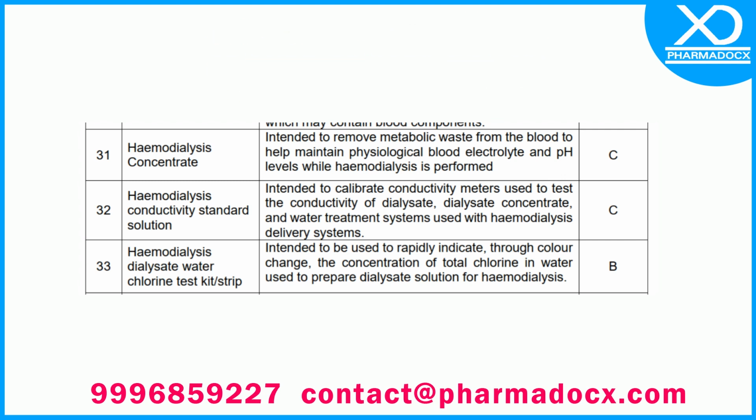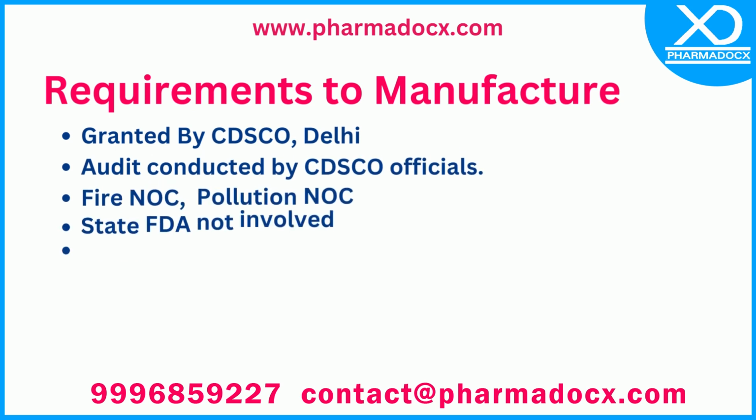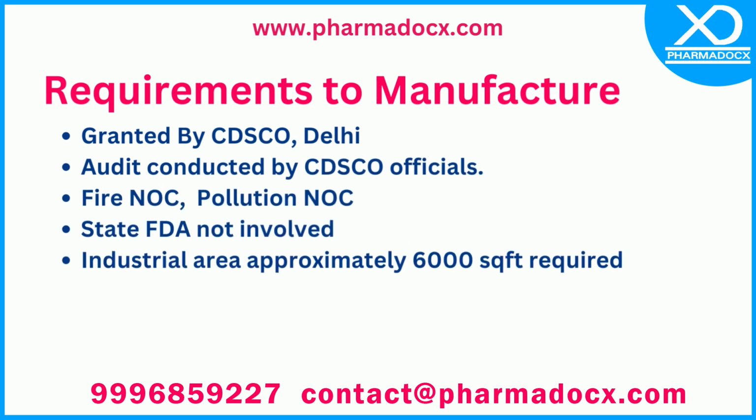Now let's discuss about requirements for manufacture of class C medical devices. The license to manufacture is granted by CDSCO headquarters in Delhi. The license has to be applied on CDSCO portal. Audit is conducted by a team of medical device officers. State FDA plays no role in the process. A fire NOC and pollution NOC is to be furnished from respective departments in order to obtain a license on Form MD9. Industrial area is mandatory in order to set up a hemodialysis factory.